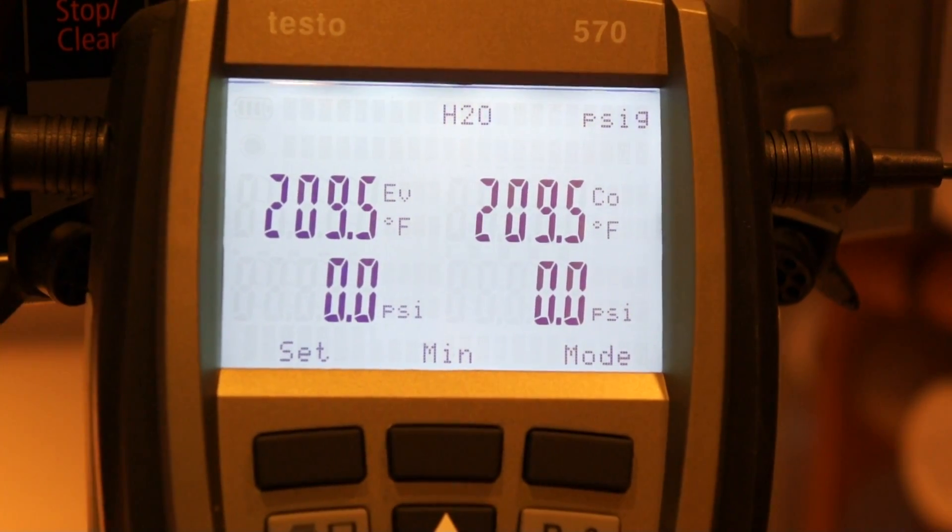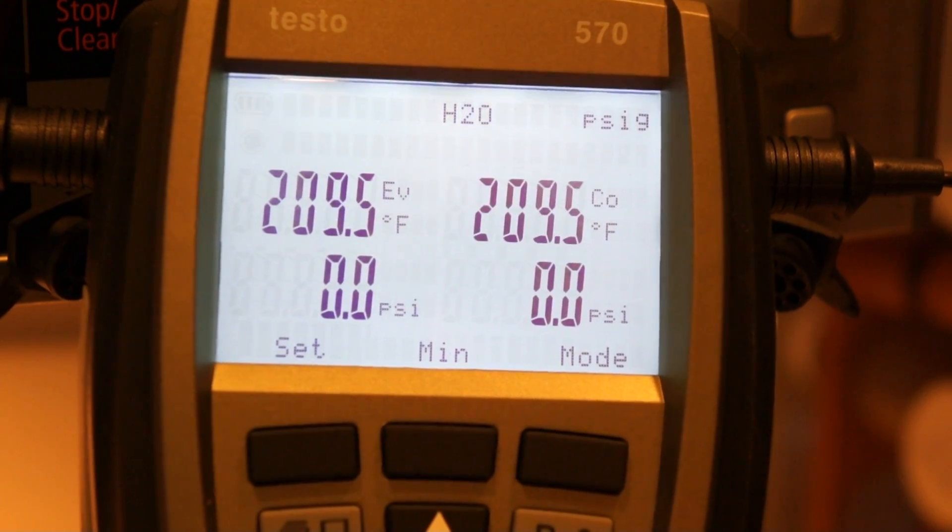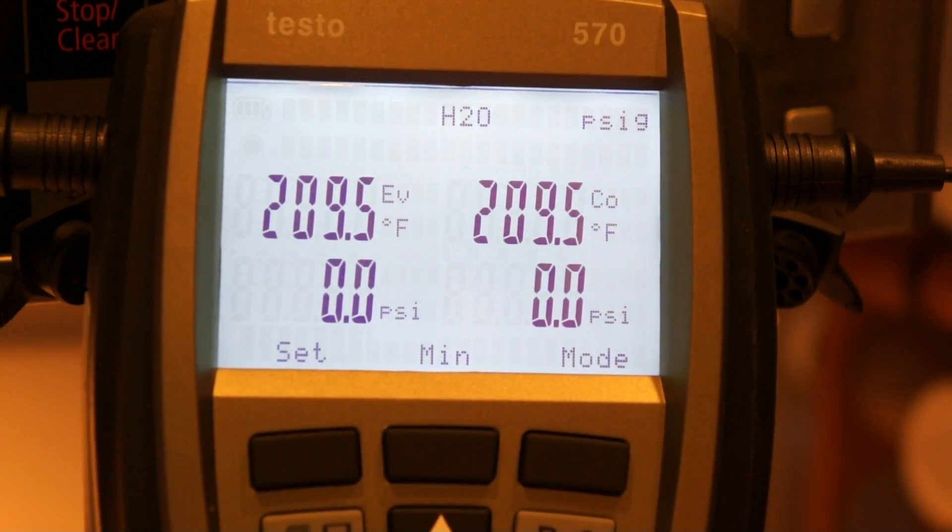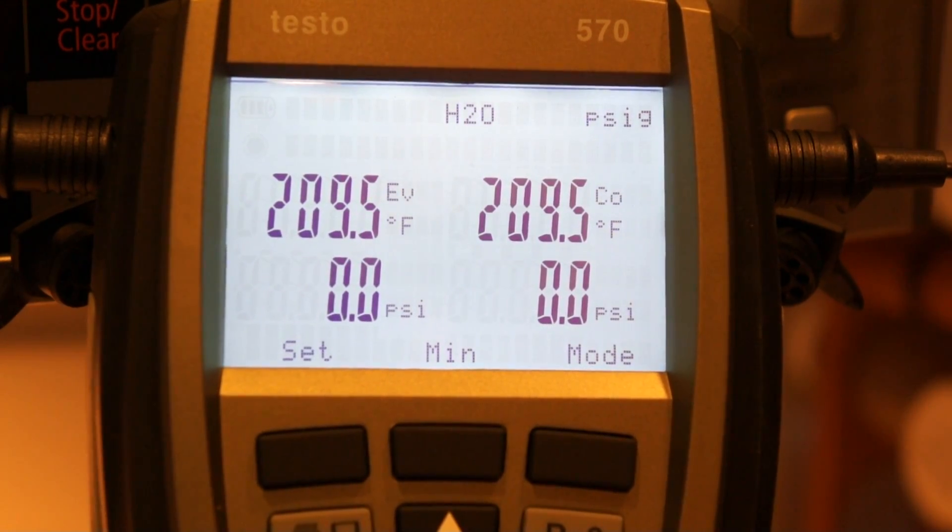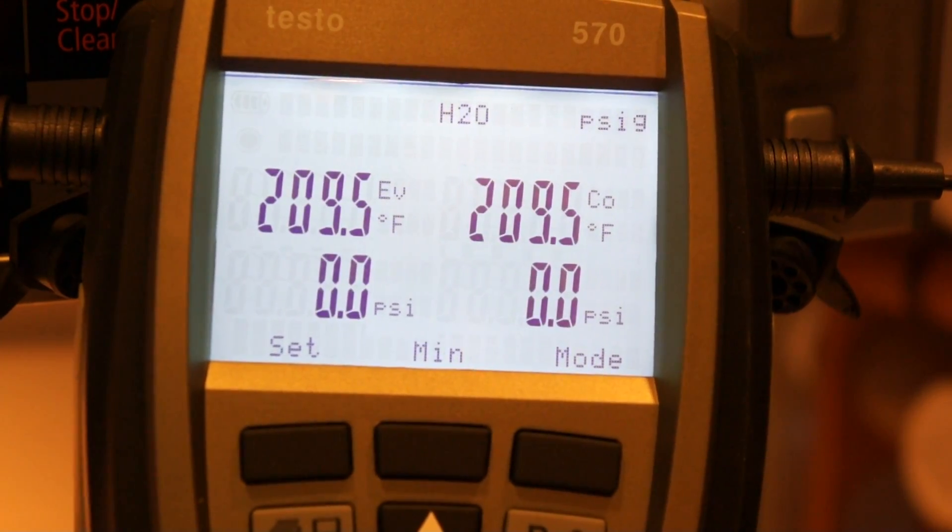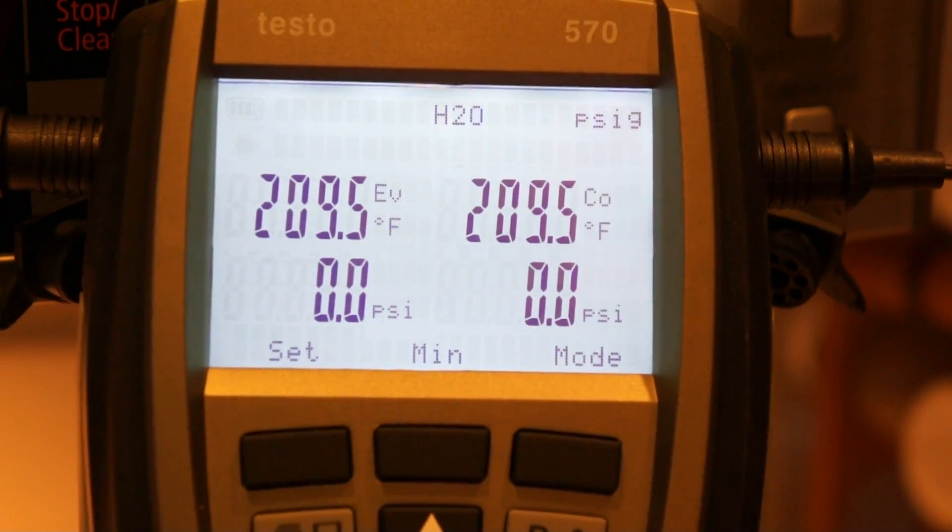So you've got to take those things into consideration. You can't calibrate pressure on its own, you can't calibrate temperature on its own. They're independent measurements and their errors will compound. So you have to take those things into account when you're making a measurement.